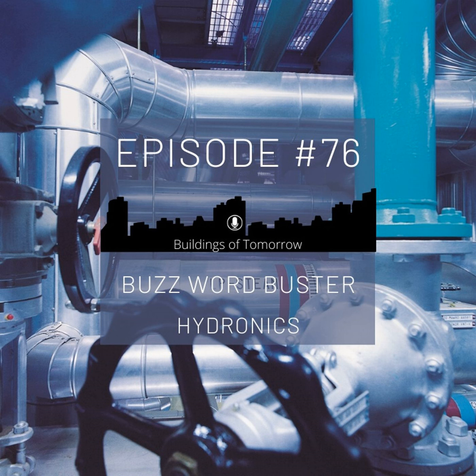So you always have a balanced system at 50% of load, at 70% of load, and not only clearly and fully balanced at 100% of load, like this was done in the past with static balancing. So here again, the trend is to move towards hydronic dynamic balancing, and this can be achieved, for example, utilizing PICVs.